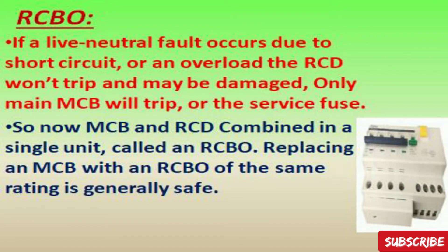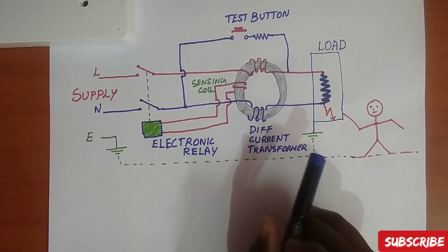What is RCBO? It is a residual current breaker with over-current protection. Since the RCD won't trip during a short circuit or overload — and may be damaged — while the main MCB trips or the service fuse fails, the solution is to combine MCB and RCD into a single unit. This combined device is called an RCBO. In homes and offices, MCB and RCD are used separately, but replacing an MCB with an RCBO of the same rating is generally safe.